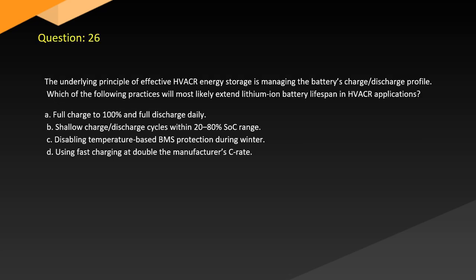Question 26. The underlying principle of effective HVACR energy storage is managing the battery's charge-discharge profile. Which of the following practices will most likely extend lithium-ion battery lifespan in HVACR applications? A. Full charge to 100% and full discharge daily. B. Shallow charge-discharge cycles within 20-80% SOC range. C. Disabling temperature-based BMS protection during winter. D. Using fast charging at double the manufacturer's C rate.